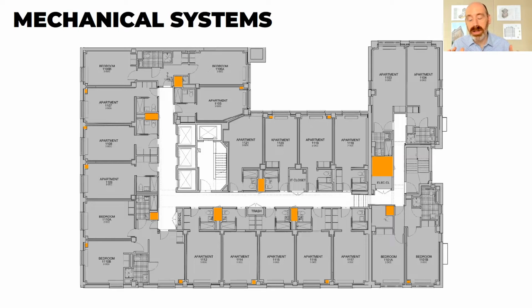But we were able to introduce these new modern systems and ductwork without creating any new shafts. That was significant in terms of cost savings — not having to do new structure or new slab openings — and in terms of space savings, not impacting the bed count in any significant way. The water side again was located next to the fan coil units adjacent to the exterior wall.